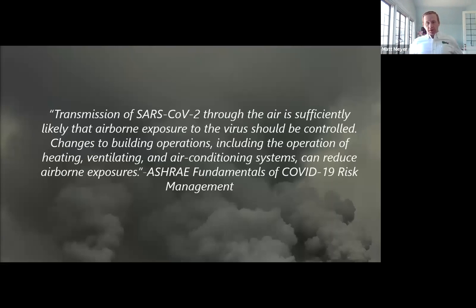So the transmission of SARS-CoV-2 through the air is sufficiently likely that airborne exposure to the virus should be controlled. Changes to building operations, including the operation of heating, ventilation, and air conditioning systems, can reduce airborne exposures. That's straight out of ASHRAE. So their first recommendation is to start increasing your outdoor air to some degree.